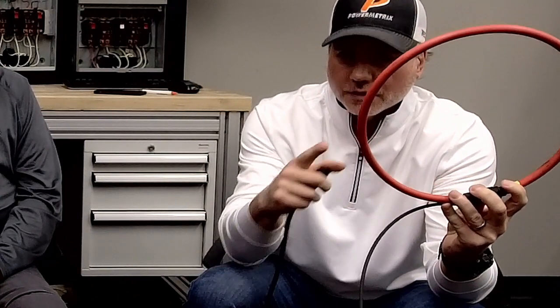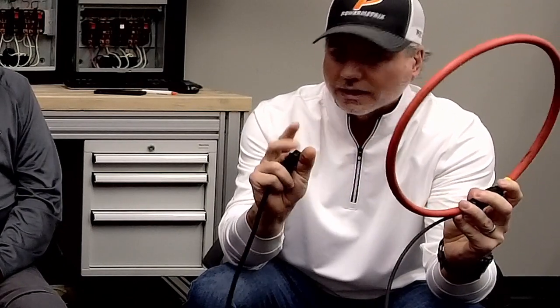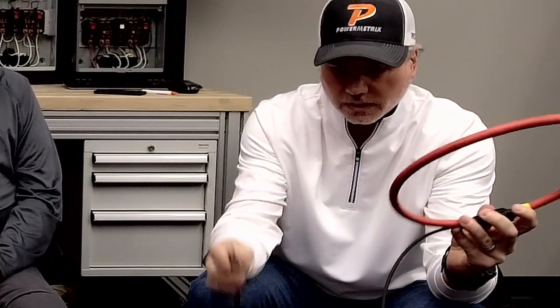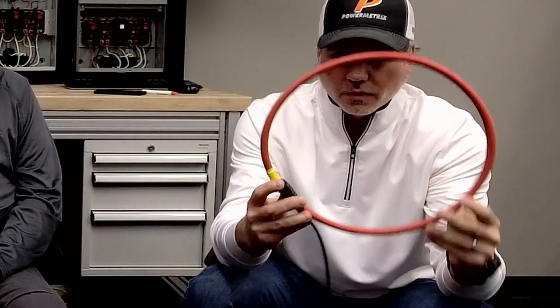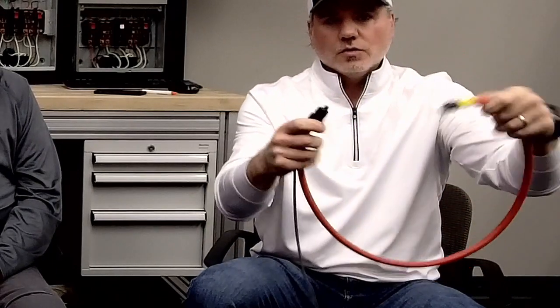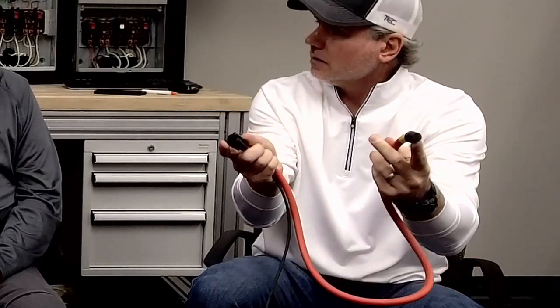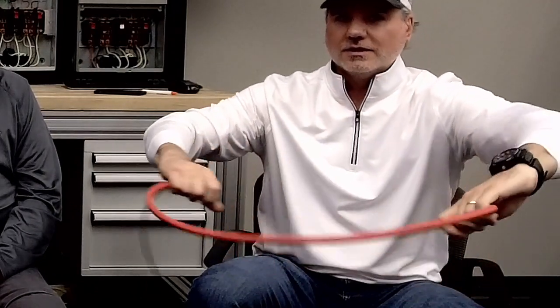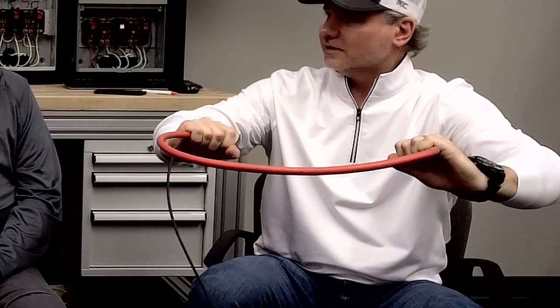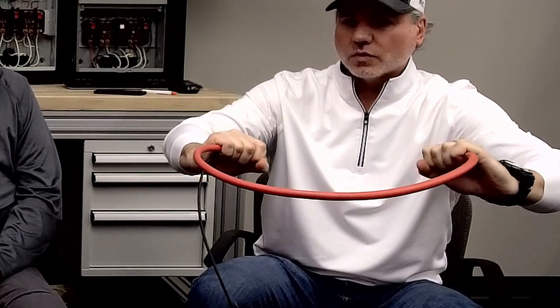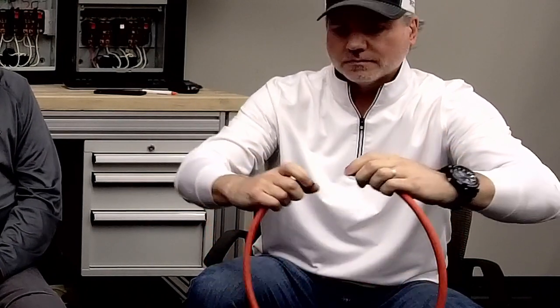We can't change the physical nature of this probe, but we can try to zero it out. That's why we calibrate them in-house. Now, if you know anything about Rogowski coils, there's no metal-on-metal connection here, right? So you can actually have this around your conductors like that and still get a reading. So the question is, how do we get the best readings in the field?